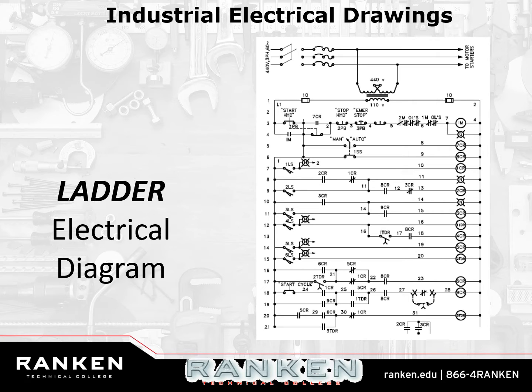What are the obstacles? I have a limit switch right here, right? That's what that drawing is, or that symbol is. It's a limit switch. Limit switch looks like number 3 LS. I can't really read it. Yeah, number 3 LS. Number 3 limit switch has to close, or what? Number 3 CR contact has to close, and number, what is that?